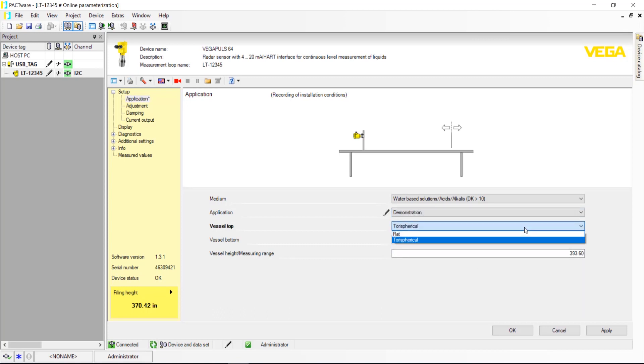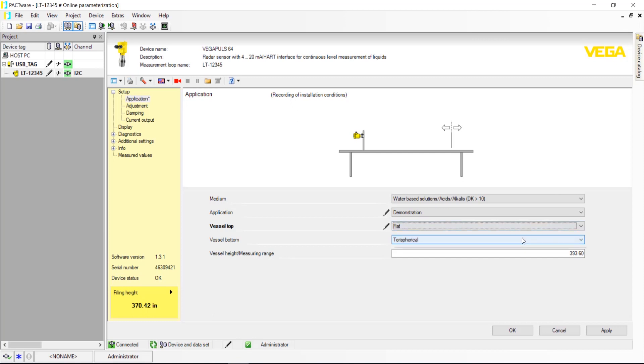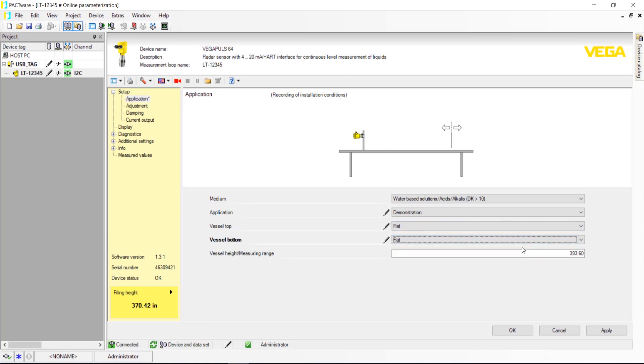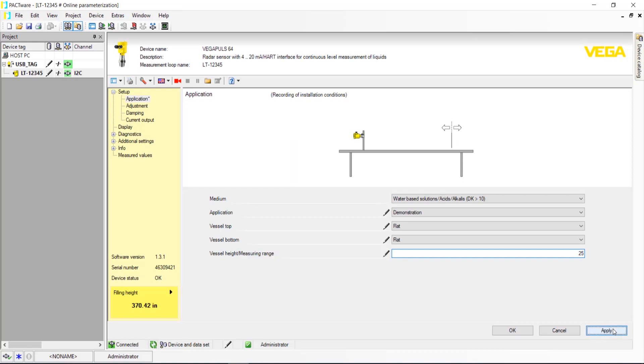Vessel Top and Vessel Bottom gives the sensor an idea of the shape of the vessel. Vessel Height/Measuring Range is the distance from the radar reference point to the lowest point in the vessel where the radar signal will reach. Once everything is selected, click Apply.